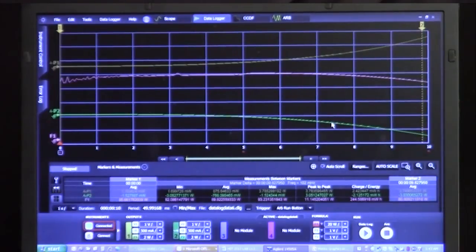Okay, fantastic. We're done. So now there's 10 seconds of sweep time across the screen here. Now what I'm showing in these two colors, the top trace, the yellow trace, is the input power starting at zero power and sweeping up as more power is pulled out of the device under test up to its full output power of a few watts.